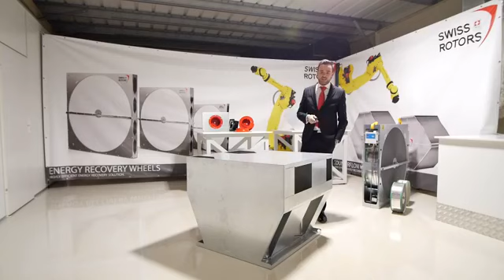When we're looking at the advantages when it comes to energy recovery on this, the most important thing we have to remember with any kind of air handling unit is that we need to be sticking to the legislation and the guidelines. So for our industry now, we're focusing towards ERP 2018, which is a minimum of 73% efficiency. But we also need to do that whilst maintaining a low pressure drop in order to keep the unit very competitive. So by maintaining this low level of pressure drop, we can keep the specific fan power low for the air handling unit whilst also getting the bonuses for having a very high level of efficiency.